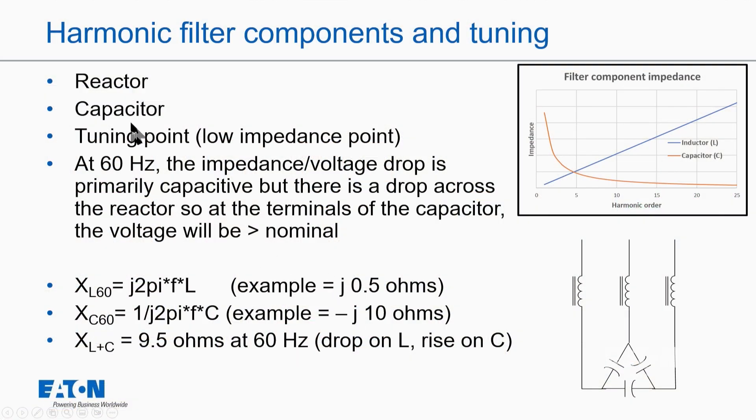So if I take and look at creating a harmonic filter, I have a reactor, a capacitor, and then I decide on a tuning point. That tuning point is the low impedance point. It's where I'm going to tune that filter to take out the harmonics of the power system, or at least reduce the harmonics in the power system.